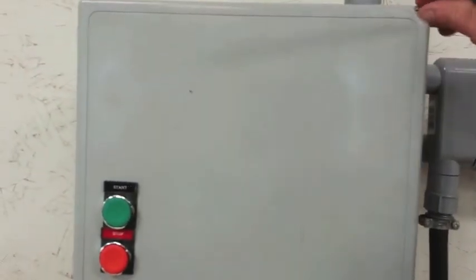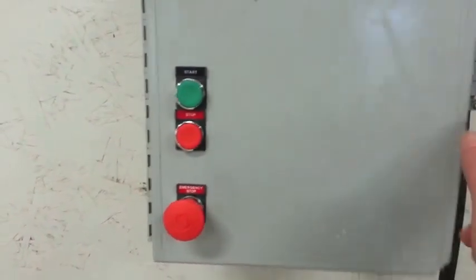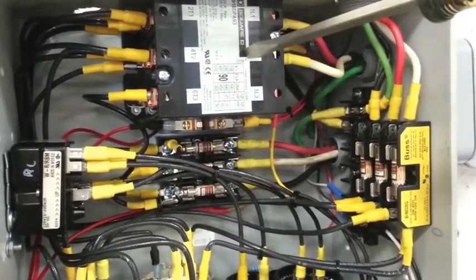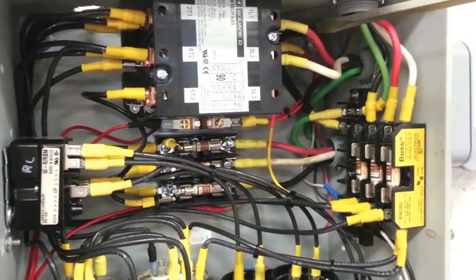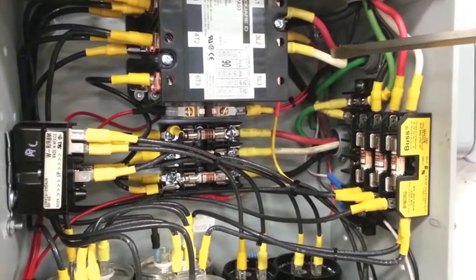I'm going to show you a few things inside. Start button, stop button, and emergency stop. We've got a 90 amp three-phase motor starter. This is single-phase power coming in here and here.